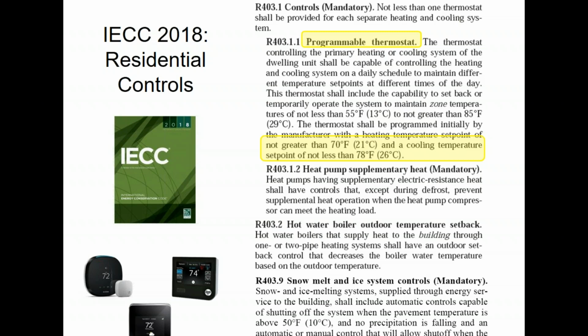If you're doing a heat pump with supplementary heat, you have to have controls that interlock it to the rest of the heating system, so that you don't run cooling with heating and stuff like that. The boiler, if you have a boiler system residentially, it has to have outdoor air reset on it. That should not be a surprise anyway, because since 2012, all boilers nationally have to have outside air reset. So you should already be doing this, and if you're not, you've been doing it wrong from the national perspective.